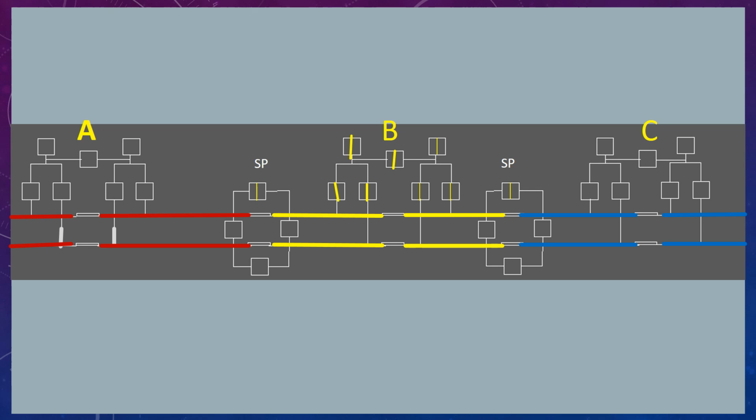So, in previous learning, we have observed that penalty from the state electricity board will be imposed if you cross the contract maximum demand and for low power factor. Contract demand is expressed in MVA, mega volt ampere. So the multiplication of voltage and current will increase the MVA if any one of these is increasing.